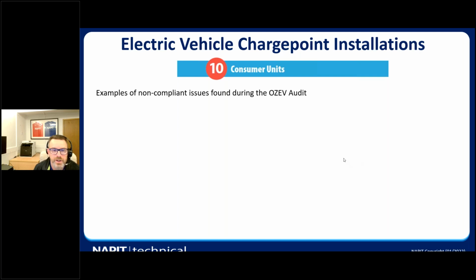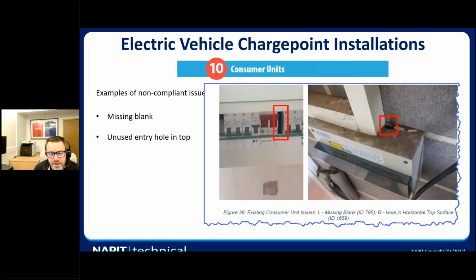We have some examples of issues with the consumer units that were found during OZEV audits. We're missing blanks on these empty holes in the tops of consumer units. These are examples where you've got a missing blank here, and to the right hand side here. You can see the EV circuit being identified, but it's in here and covered in there. And we've got a missing blank at the top of the charge point here as well.